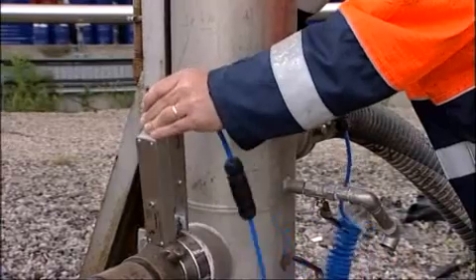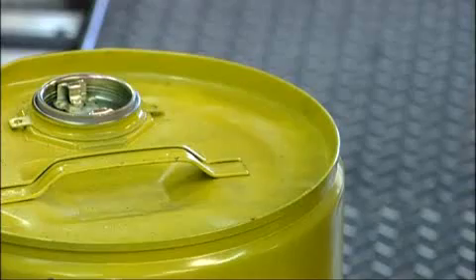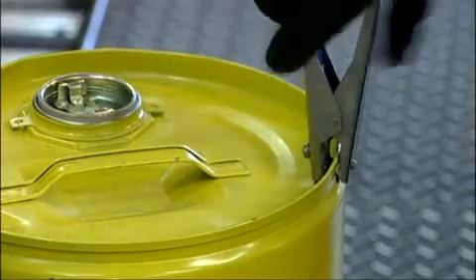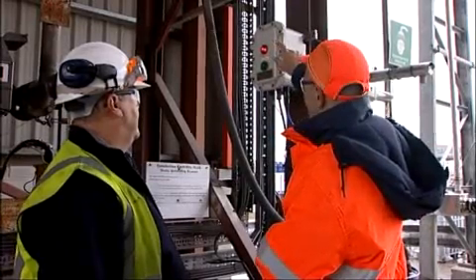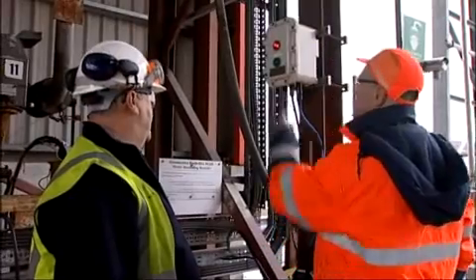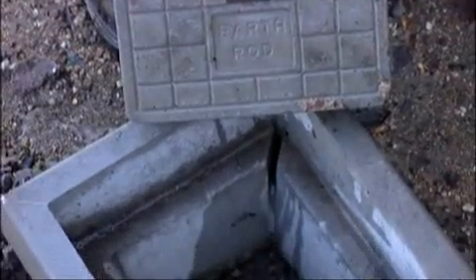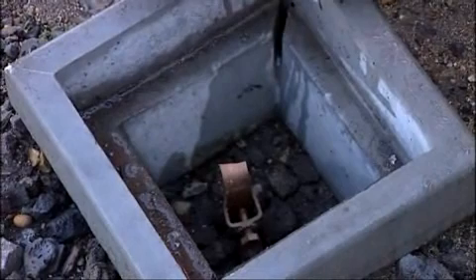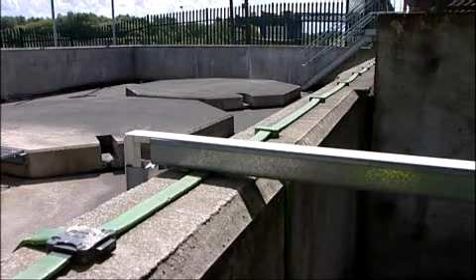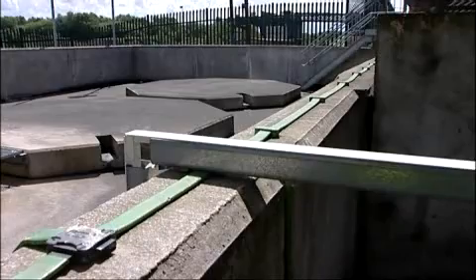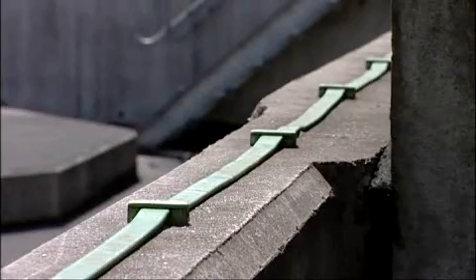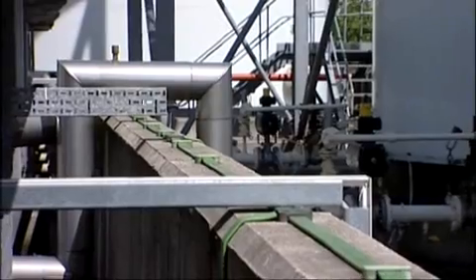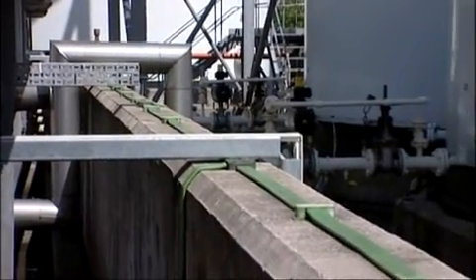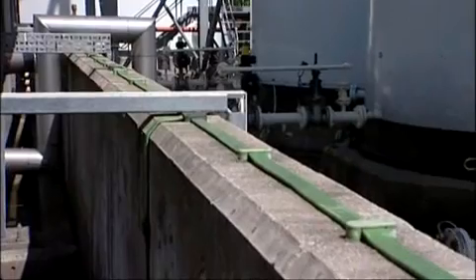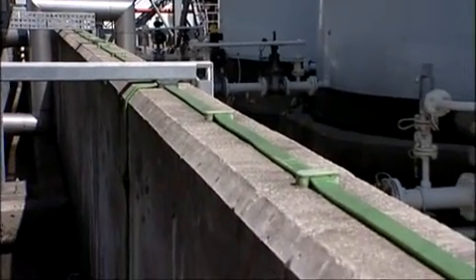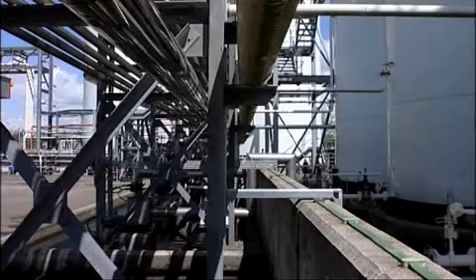To ensure a high level of static electricity awareness is maintained, there should be regular testing of equipment with results logged, frequent awareness training of operators, and reference to the appropriate standards. The fixed part of the earthing system, the earthing rods, the earthing loop, bonding on fixed equipment should be tested periodically, usually by a specialist, often in conjunction with tests on lightning protection equipment. A typical test period would be 11 or 13 months, testing during different seasons, and would look for any significant variation from previous tests, indicating deterioration.